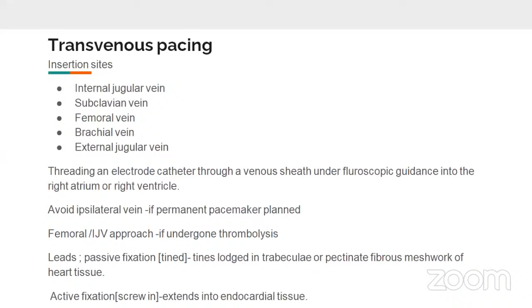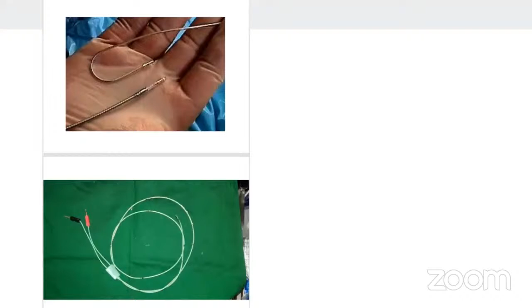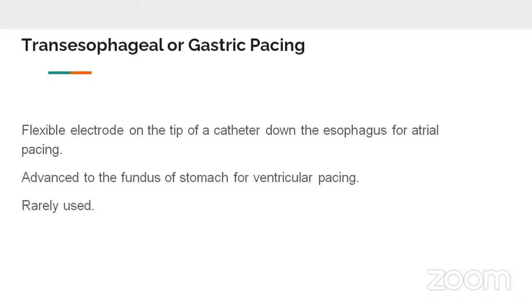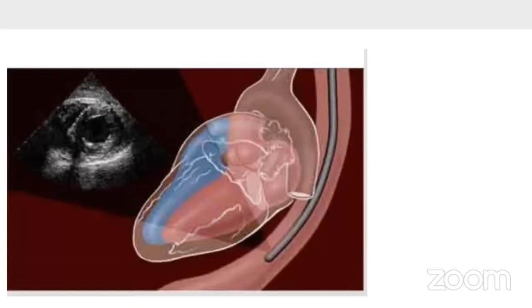Leads used for transvenous pacing include passive fixation, which has tined ends lodged in the trabeculae or the pectinate muscles of the heart tissue, whereas active fixation is a screw-in type that extends into the endocardial tissue. This is a lead used in the transvenous catheter. Transesophageal or gastric pacing uses a flexible electrode on the tip of a catheter passed down the esophagus for atrial pacing and advanced to the stomach for ventricular pacing.